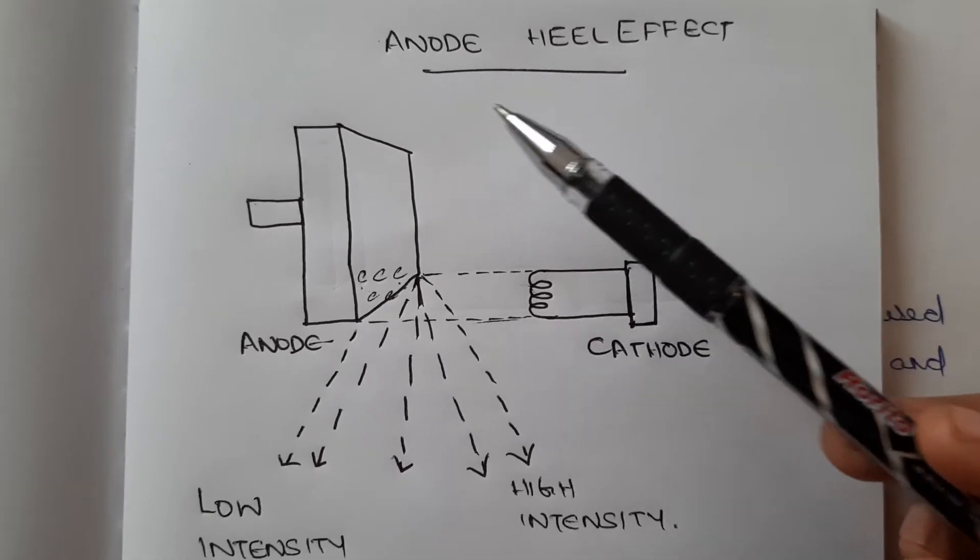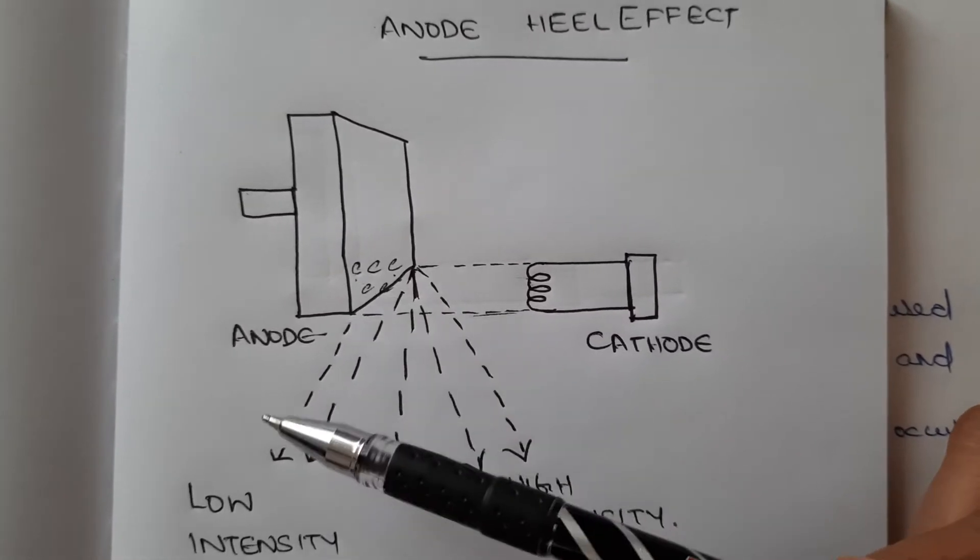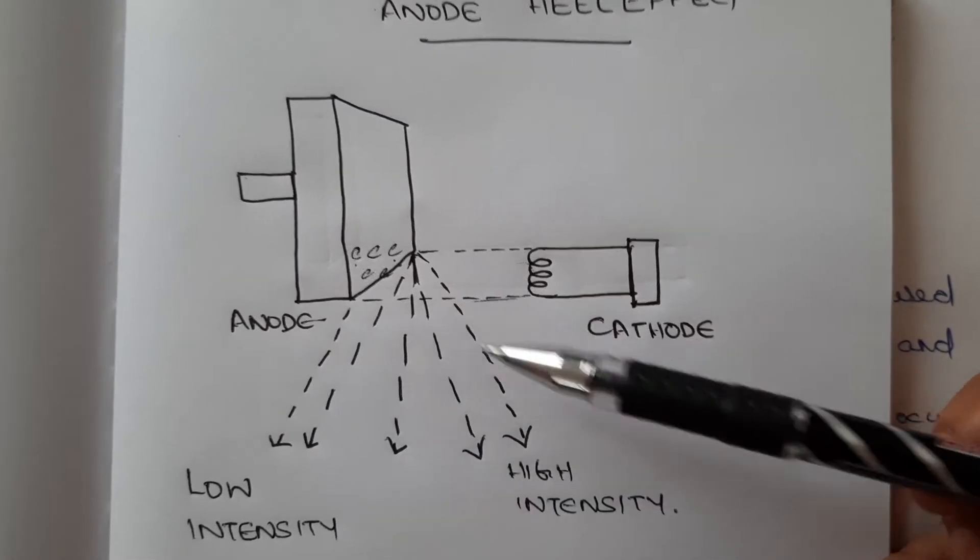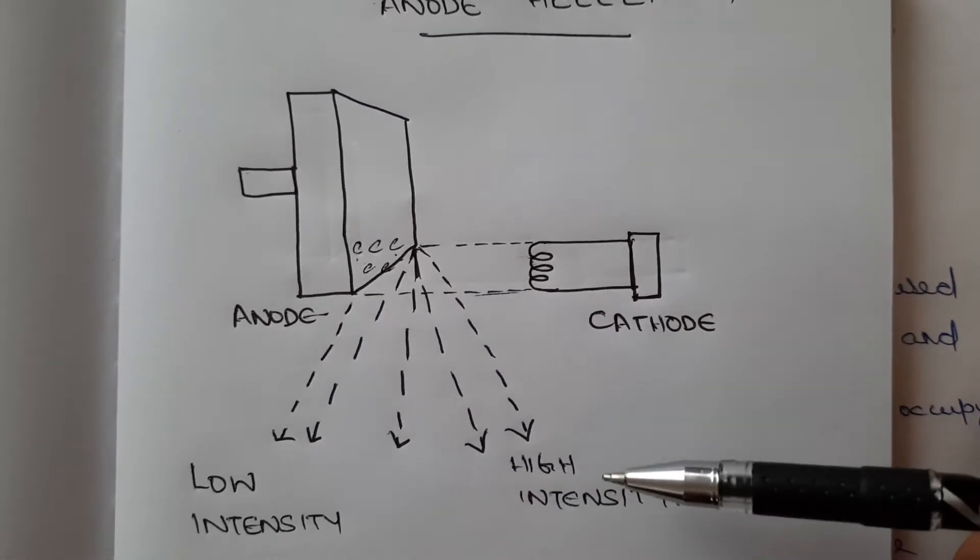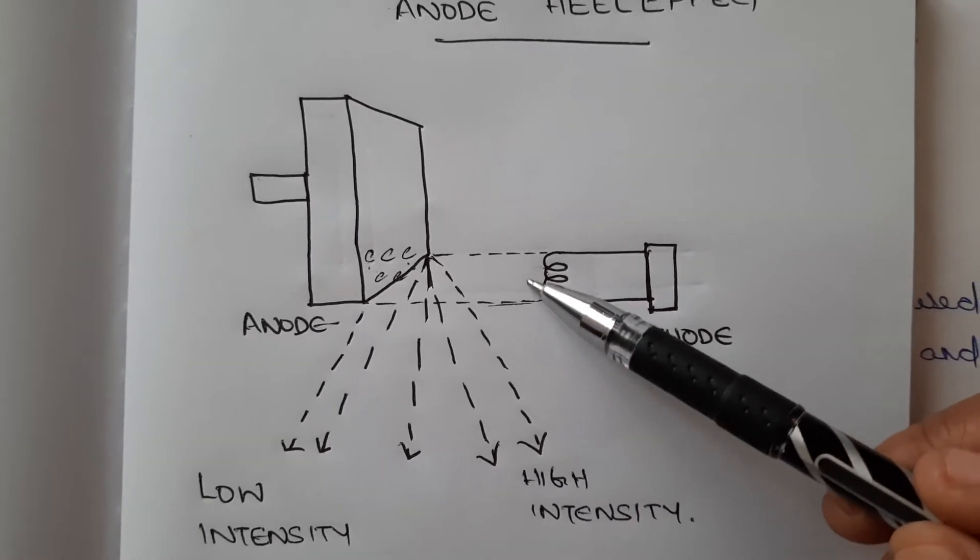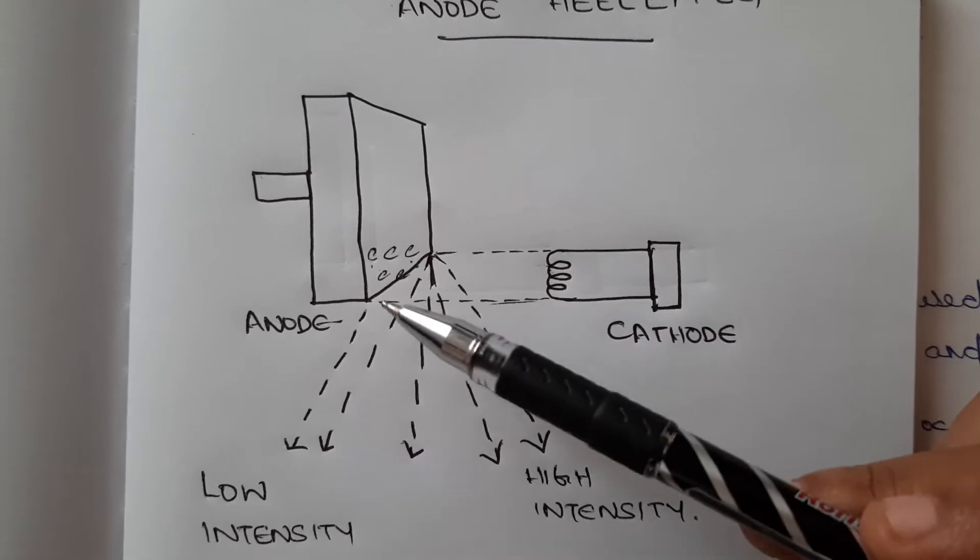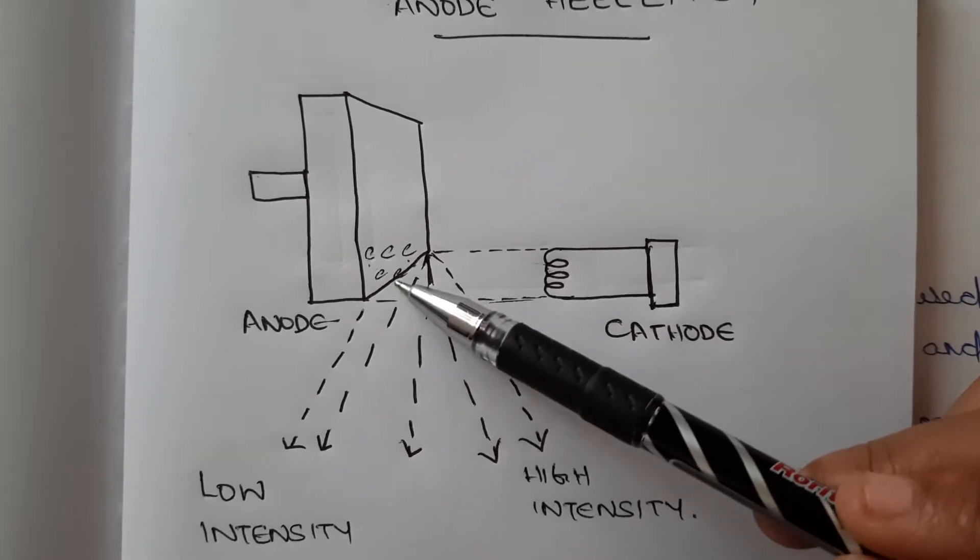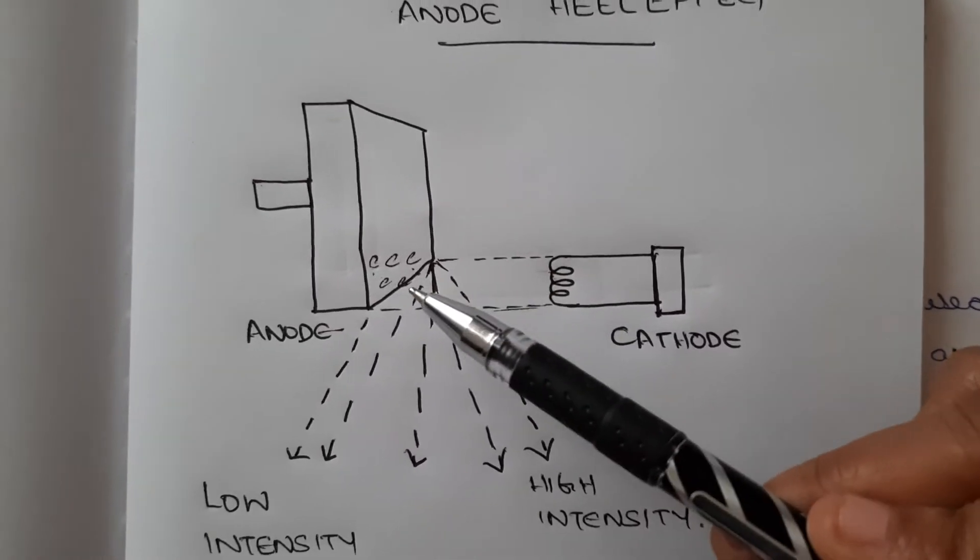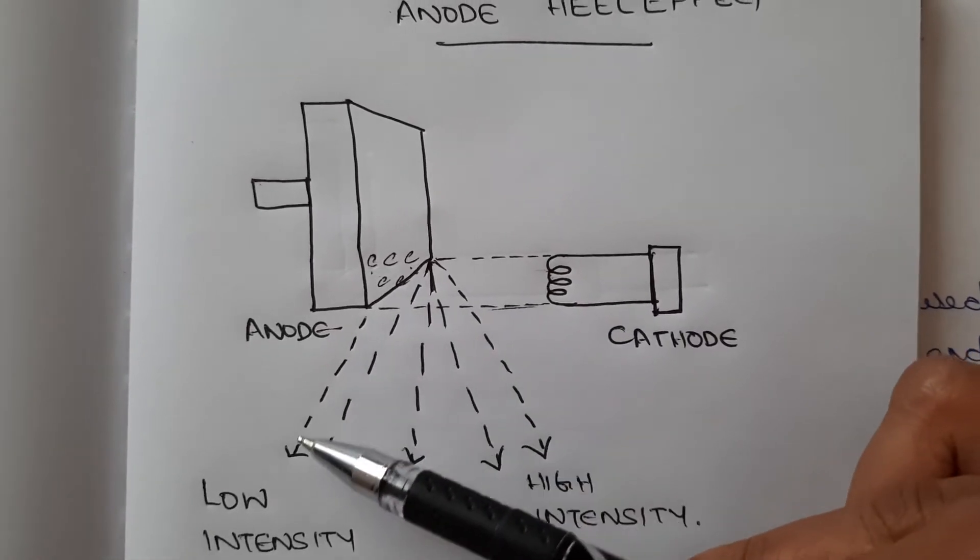As a result of the anode heel effect, the x-rays produced towards the anode end are of low intensity compared to the x-rays produced towards the cathode end. Here, the electrons from the cathode are accelerated towards the anode and get absorbed in the target area.